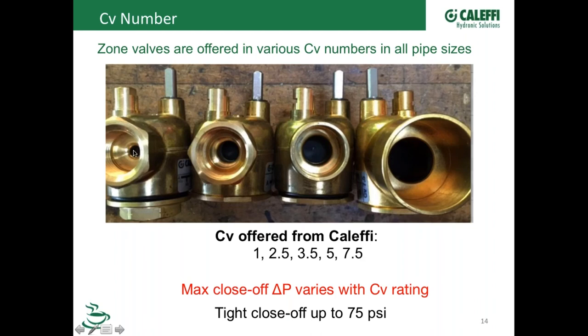So this over here would be an example of a 1 CV. And you can see the change there is the size of the port in there, the size of the hole in it. And the reason for that is this valve right here, this 1 CV valve, will shut off against 75 pounds of pressure, delta P or pressure differential. This valve over here happens to be, I think, a 1.25 inch valve, 7.5 CV, and has a 20-pound shutoff.